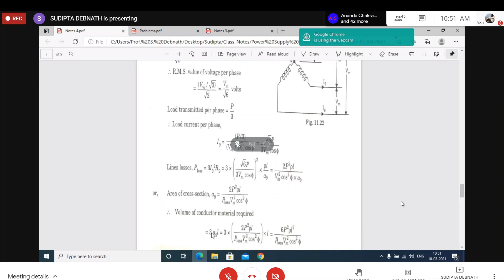So A10 will be this one. Only, instead of writing 3 here in the three-phase four-wire system, you have to consider the cross-sectional area or the volume of the neutral conductor also. And you know, when it is not carrying any current under balanced condition, we assume the neutral conductor cross-section to be 0.5 that of the outer. So with 3A9L, we have to add 0.5 A9L. So it will be actually A10. This system is the last system, the 10th system. So you write 3.5 A10L. Actually A10 will be exactly equal to, you substitute this value, ultimately you will be getting 1.75. Actually it is slightly higher as there is a fourth conductor.